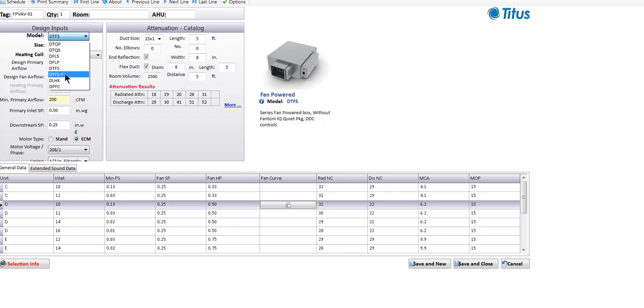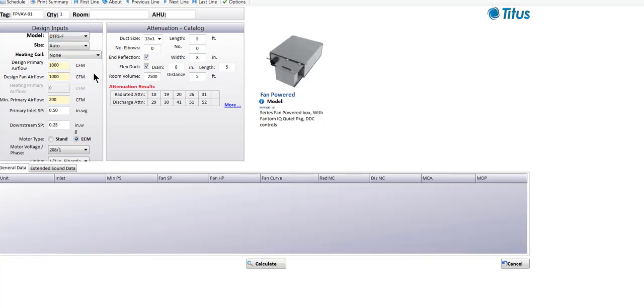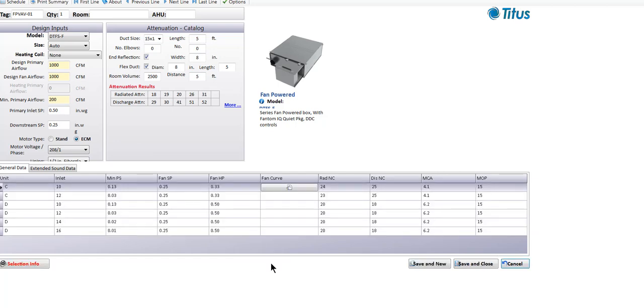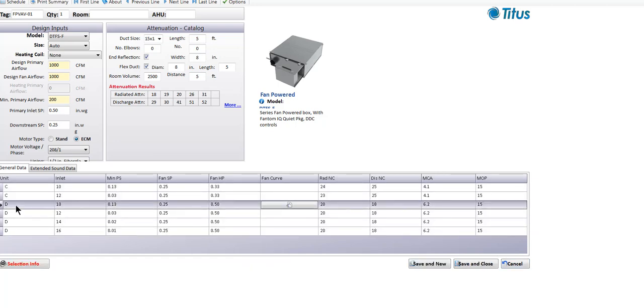With the standard DTFS we've got NC31 radiated and NC24 discharge. If we go with the phantom version of this box and make a new selection, we come right back to our unit size D, but we've dropped the radiated sound level all the way from NC31 down to NC20, and our discharge sound went from NC22 down to NC18. An 11 point drop in radiated sound is huge, and we achieved that with our pull-out sound attenuator.